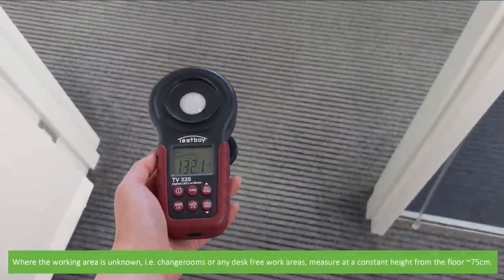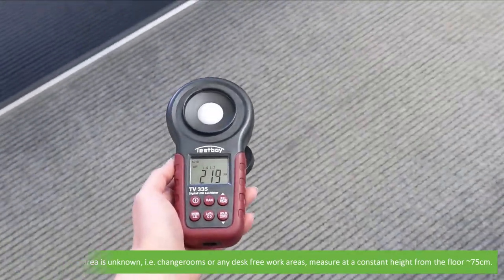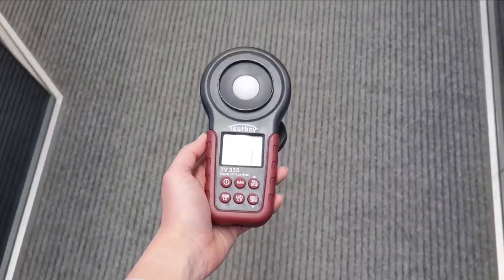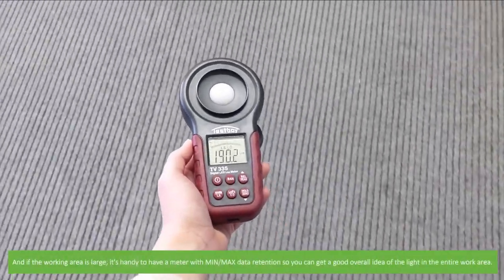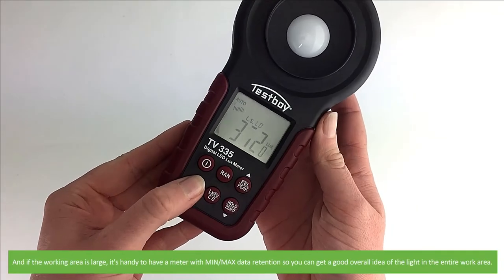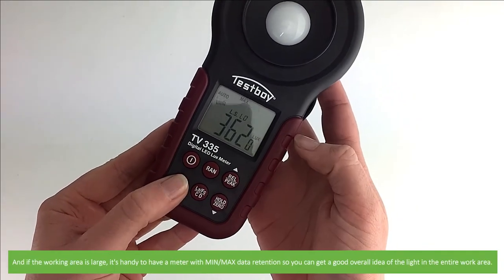Where the working area is unknown — for example, changerooms or any desk-free work areas — measure at a constant height from the floor, around 75 centimetres. And if the working area is large, it's handy to have a meter with minimum and maximum data retention so that you can get a good overall idea of the light in the entire work area.